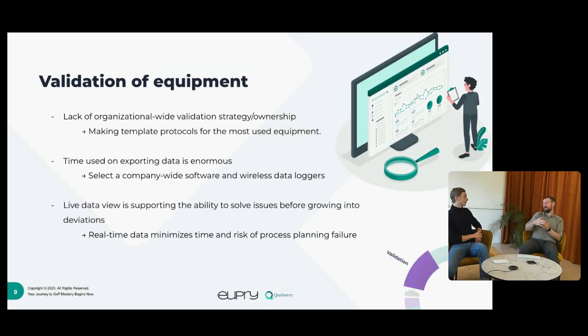I think for a large warehouse with 200, 300, 400 sensors, it really scales in terms of the amount of time that you save, because you get instant feedback on whether something is within acceptable ranges or not. So in terms of being able to automate the processes, real-time data, and then I would still say wireless data logging, is one of the major upsides.